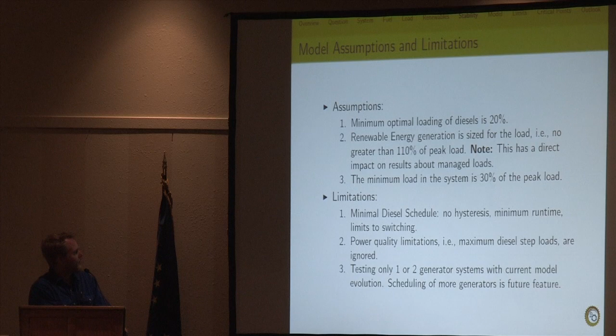Nonetheless, even in these kinds of systems, you can actually integrate quite a bit of renewable power, but it depends a lot on what your genset size is. Now we're looking at 2 gensets, and here we're seeing that one of them should be about 40% of the total load or demand size, and the other one about 60%. And you can actually get to about 70% penetration. The top penetration level here is directly tied to the amount of spinning reserve you would want to keep in your system and the minimum optimal loading that you decide on. And then the average can be around 70% if the diesel plant is laid out that way.